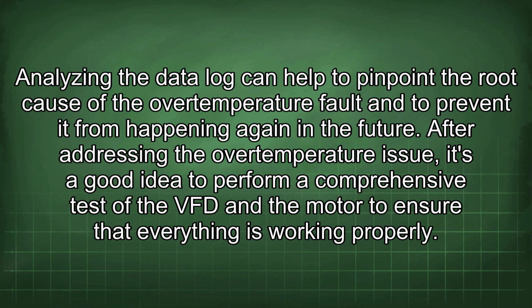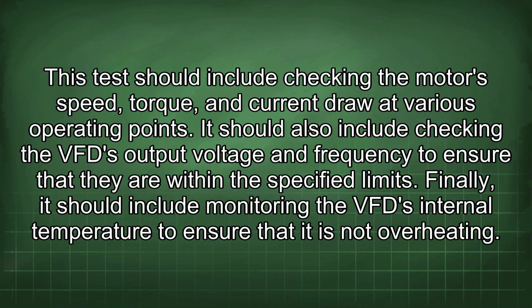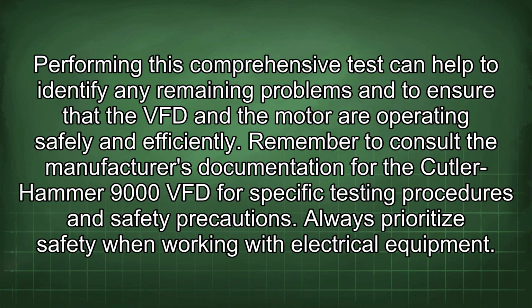After addressing the overtemperature issue, it's a good idea to perform a comprehensive test of the VFD and the motor to ensure that everything is working properly. This test should include checking the motor's speed, torque, and current draw at various operating points. It should also include checking the VFD output voltage and frequency to ensure that they are within the specified limits. Finally, it should include monitoring the VFD internal temperature to ensure that it is not overheating. Performing this comprehensive test can help to identify any remaining problems and to ensure that the VFD and the motor are operating safely and efficiently.